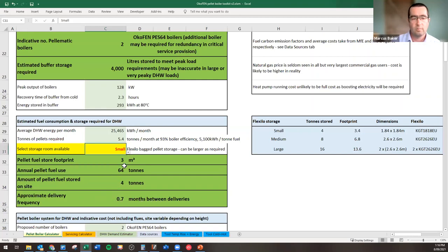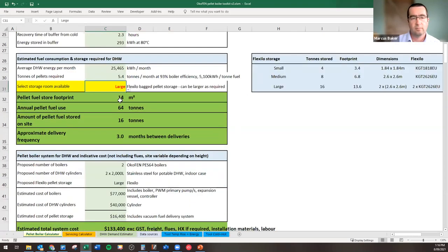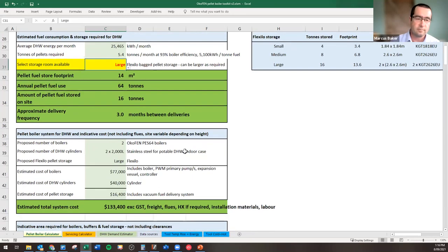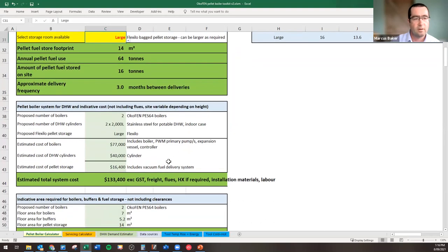Whereas if you can give a bit more room, we've got a footprint here of how much pellet store it's going to take up, what it's going to store, annual fuel use, and therefore how frequently. So now we've got 3 months between deliveries. So you see, it makes quite a big difference. With small we'd have to have delivery less than every month, medium every month and a half, and large every 3 months. And large still not that big. It's only 14 square meters. I know our mates in the architecture business will freak out that we've taken another cupboard off them, but that's the price you pay for combating climate change.